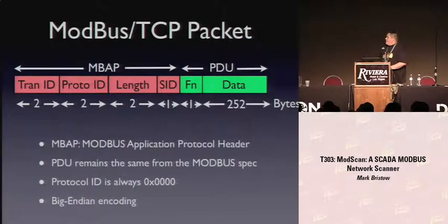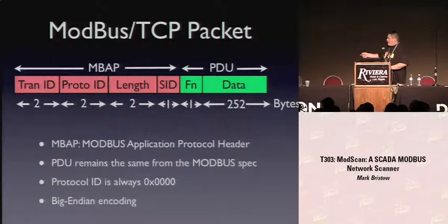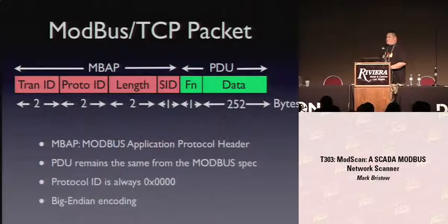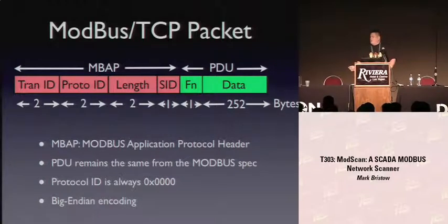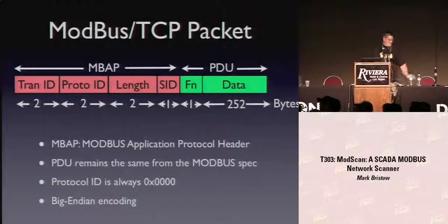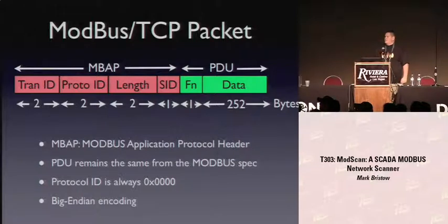This is a ModBus TCP packet. It's broken up into two major sections: the PDU, which is the same as before - the only thing you have to have for ModBus - and then you have the MBAP, or ModBus Application Protocol header, which has all your routing information. You have a transaction ID and a protocol ID, which for some reason is always zero. You never change them for any reason. Someone in the audience explained that originally the header was going to support multiple protocols in the back, so the protocol ID was there, but only one was ever developed, which is why it's always zero.